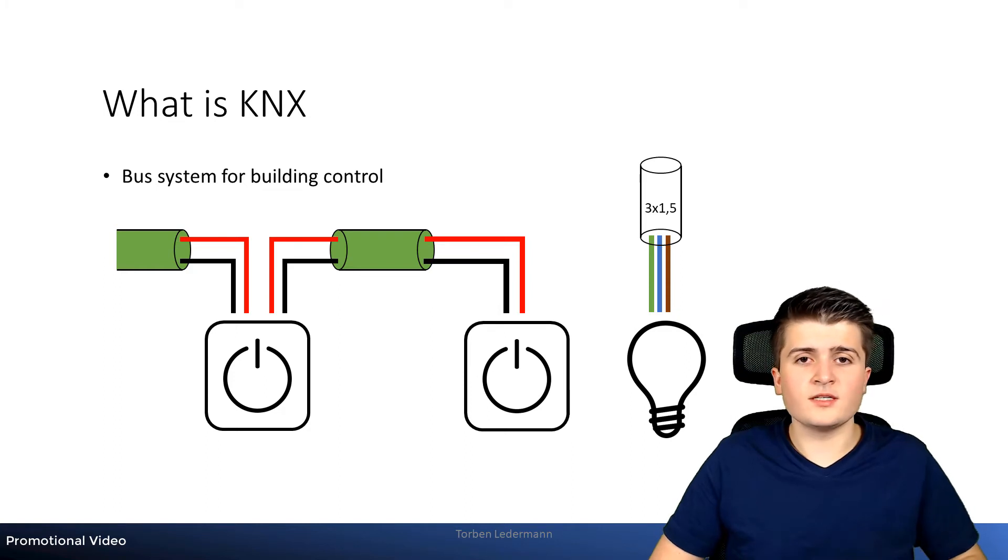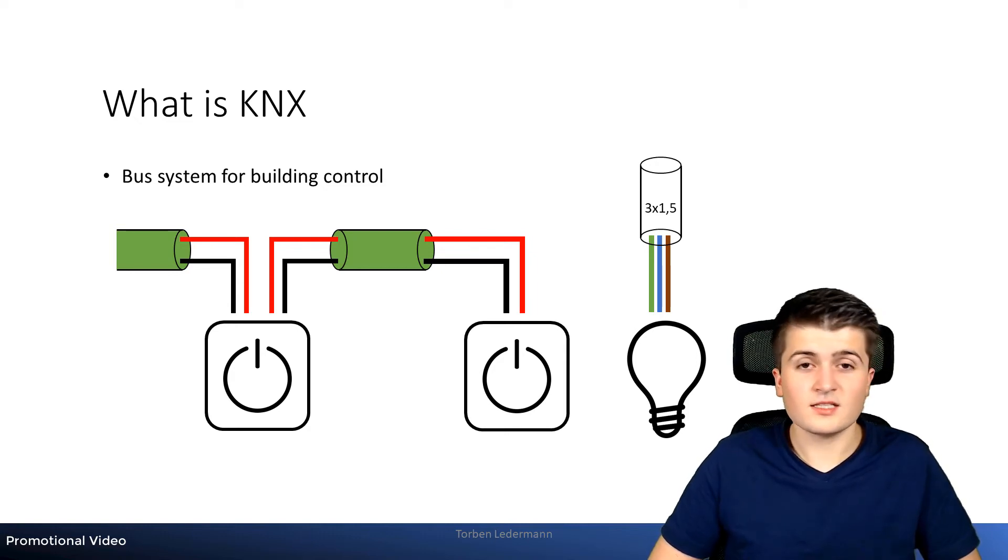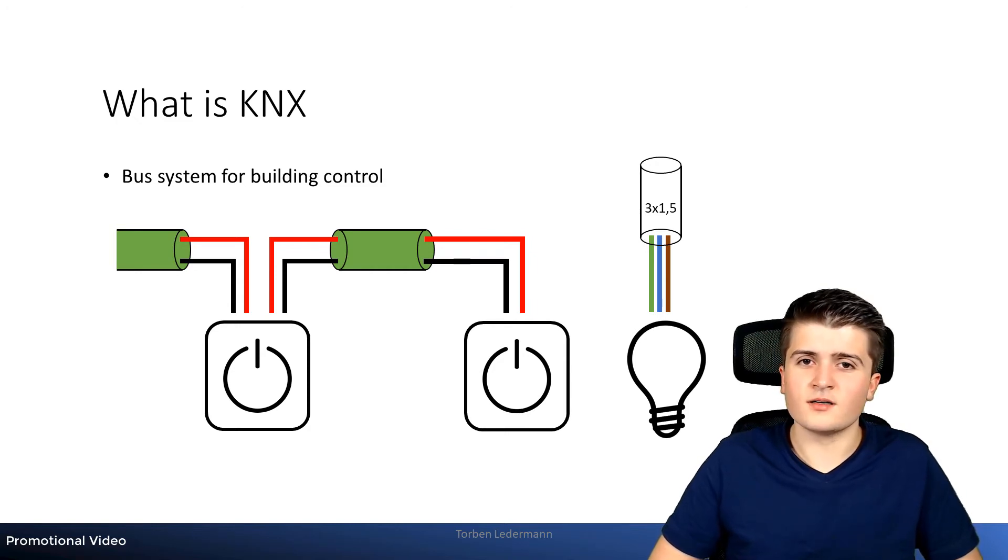And it receives the information when to switch the light on and off via the bus wire. So whenever a user presses the push button the sensor then sends a telegram onto the bus wire, which the actuator reacts to and turns the light on or off. Therefore central functions such as timers can now easily be implemented. The corresponding module only has to be connected to the bus wire and parametrized and is then capable of switching the light on and off.